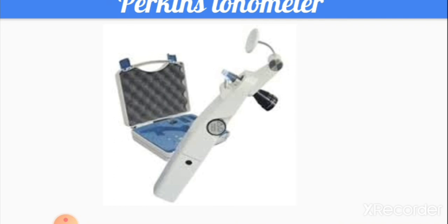The Perkins tonometer is also based on the same Imbert-Fick principle. The main difference is that the Goldmann tonometer requires a slit lamp and is not portable, whereas the Perkins tonometer is handheld. The head of the tonometer is placed in front of the patient's cornea and uses a built-in cobalt blue filter. Fluorescein staining is also required, and the working principle is the same as the Goldmann applanation tonometer.